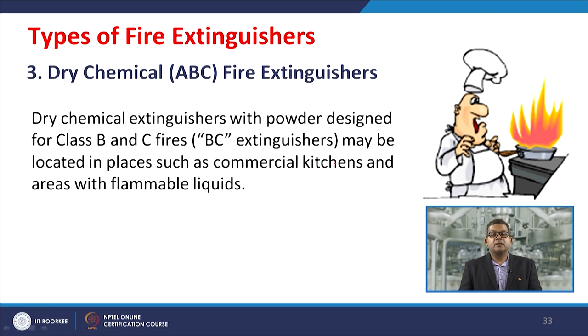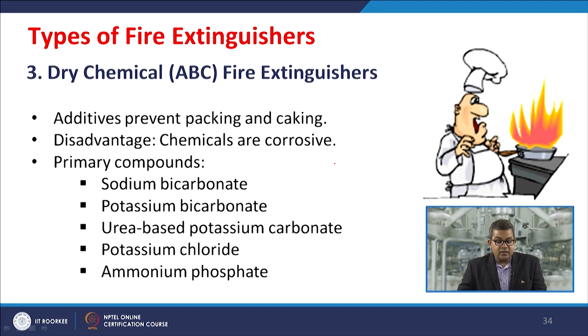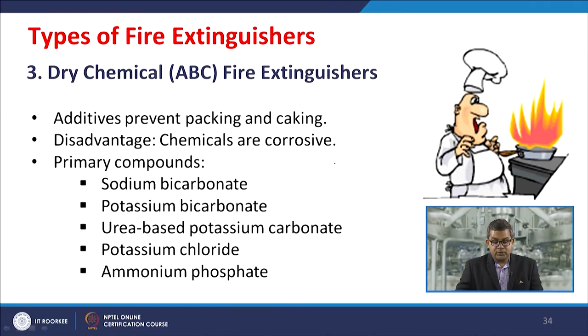Additives may be used to prevent packing and caking of the powder — sometimes the powder may form lumps, which is why some fire extinguishers have expiry dates. A disadvantage of dry chemical extinguishers is that the chemicals used are corrosive in nature. The primary compounds used include sodium bicarbonate, potassium bicarbonate, urea-based potassium carbonate, potassium chloride, and ammonium phosphates.